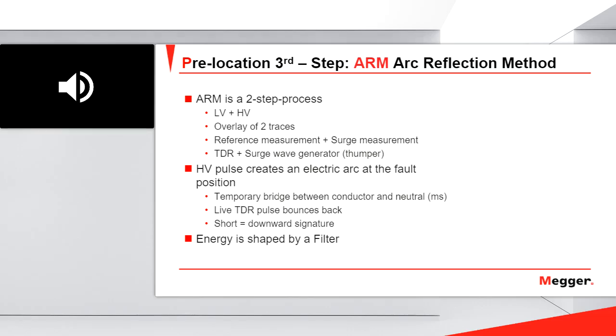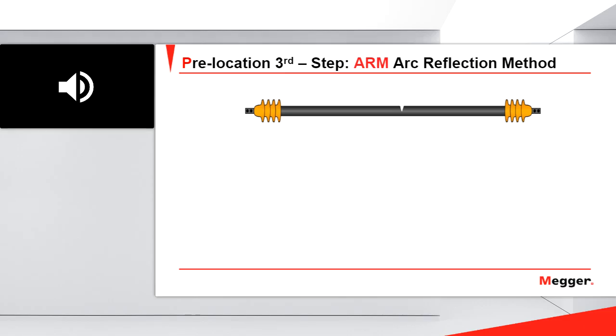We have here the same 15 kV cable. We have the fault, a pinhole fault. I connect my fault locator equipment. So the first thing that I will have is the low voltage trace. Here we have the low voltage trace. You can see that the trace looks like a splice, because at the end we have a splice between the thumper and the medium voltage cable. Then we have a flat line.